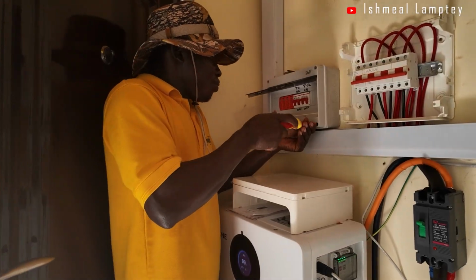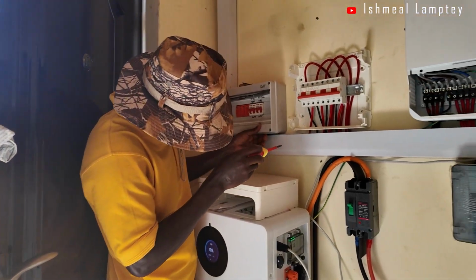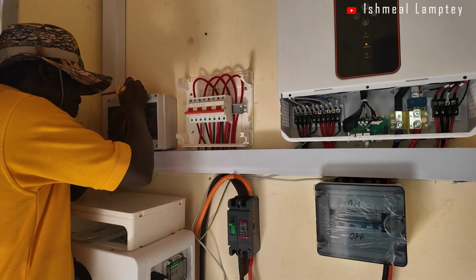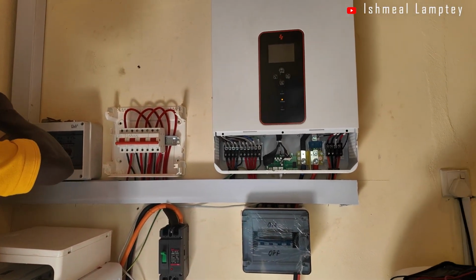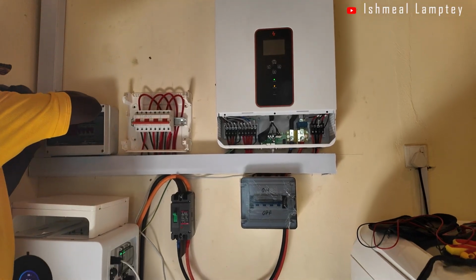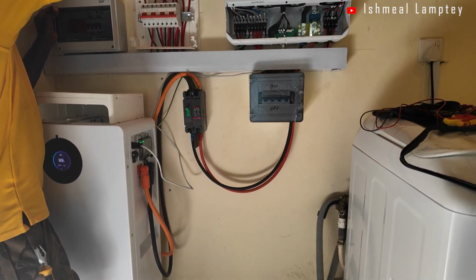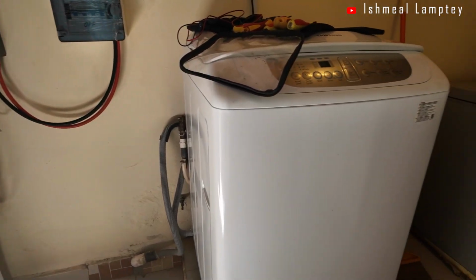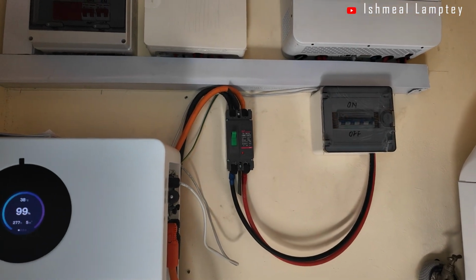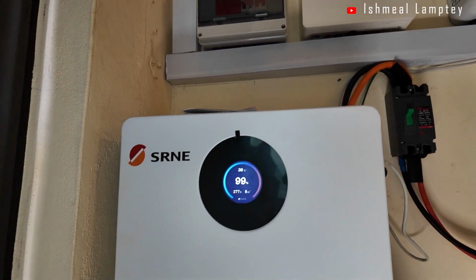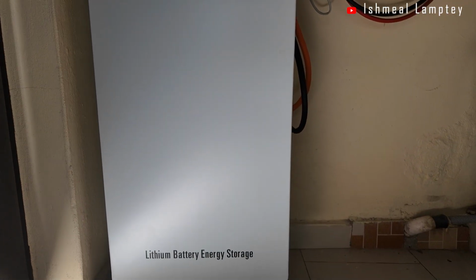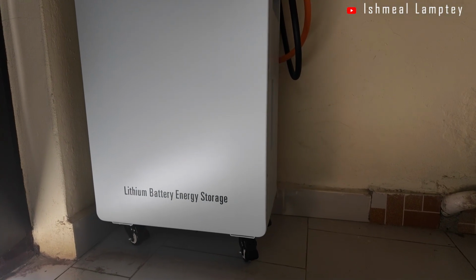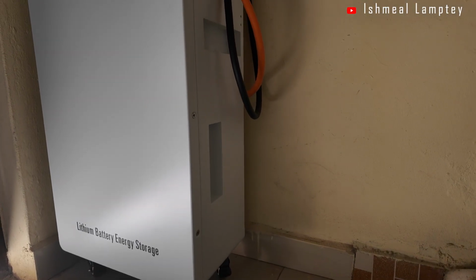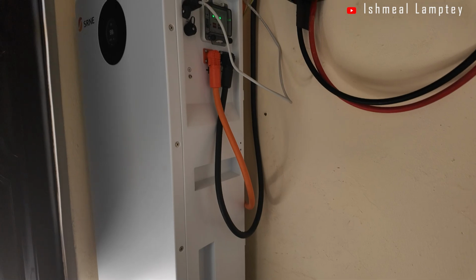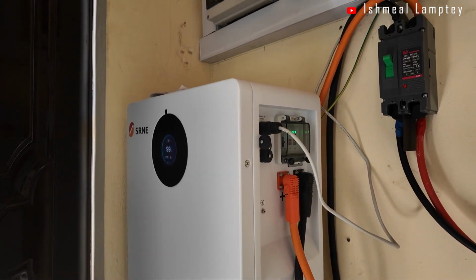Then we also installed the battery, which comes with 2 cables, positive and negative. Aside from that, you also have to connect the earth cable from the battery to either the inverter or the earth system. And then you also have to connect a network cable, or a communication cable, I should say, which helps establish communication between the battery and the inverter. It's very important they communicate so that they're able to function properly. So this was the configuration that we did in terms of the hard configuration: the cables coming in here and there, the appliances, and the systems that we used for that.